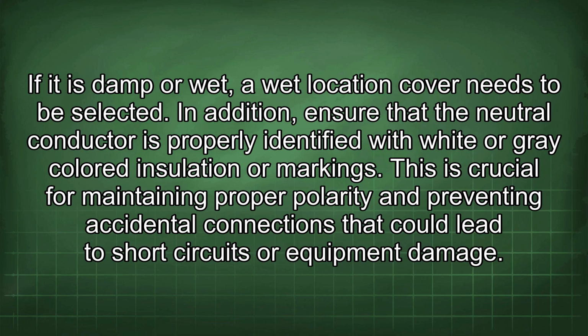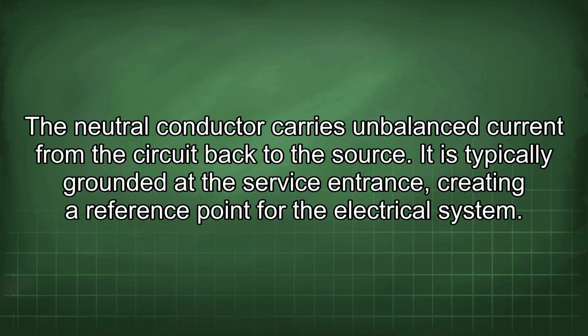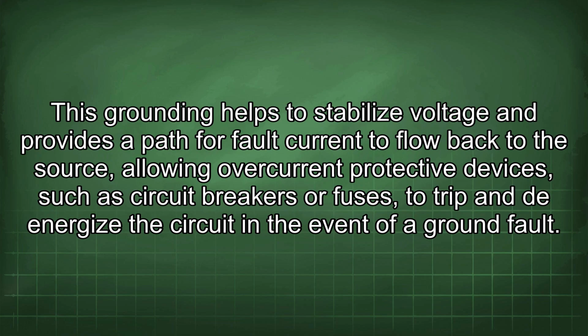In addition, ensure that the neutral conductor is properly identified with white or gray colored insulation or markings. This is crucial for maintaining proper polarity and preventing accidental connections that could lead to short circuits or equipment damage. The neutral conductor carries unbalanced current from the circuit back to the source. It is typically grounded at the service entrance, creating a reference point for the electrical system.